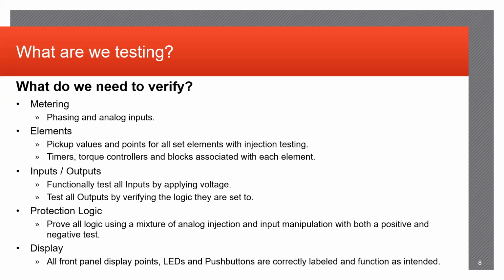Firstly, you always start with a metering test on the relays to verify the phasing and the amplitude of the currents and voltages going into the relay. This is done to verify the correct ratios are being used not only on the relay side, but that it matches up with the design side, whether that be on the prints or even on the equipment itself. Different elements such as timers, torque controllers, any blocks associated with each element, these will be tested usually with pickup values regarding current measurements that have been calculated by the system protection engineer. And our job is to verify that the relay correctly identifies these elements and operates when need be.